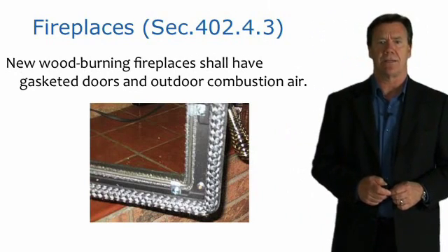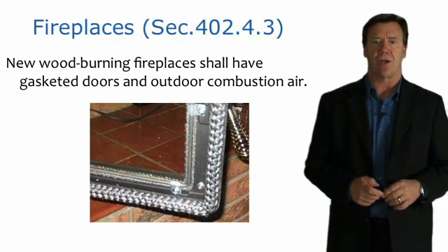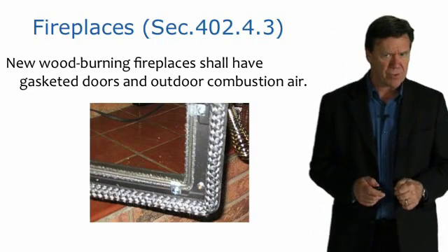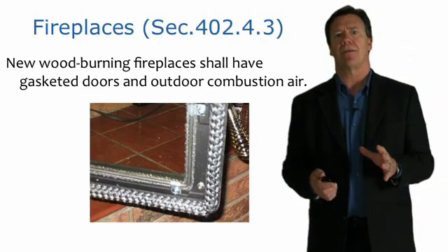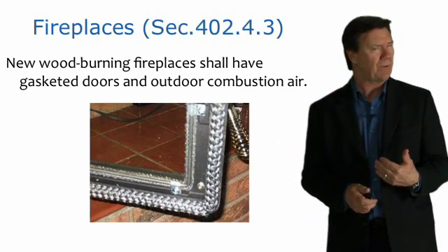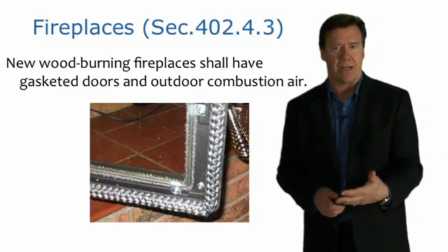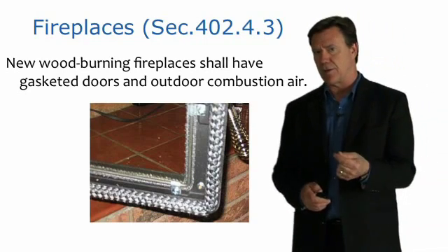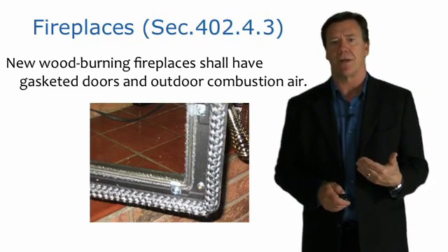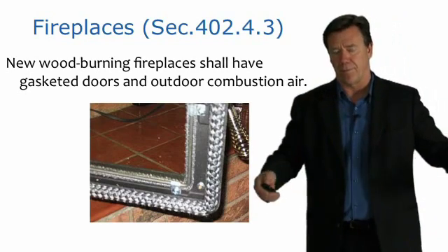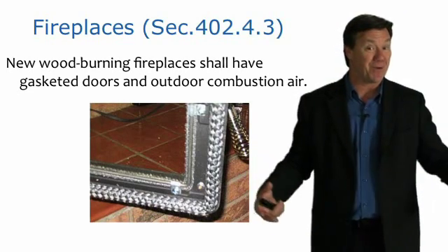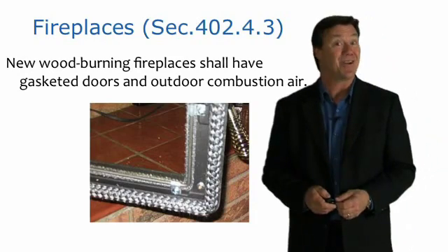Another code requirement is that wood-burning fireplaces shall have gasketed doors and outdoor combustion air. There have been reports around the country of fireplaces not engineered well enough to handle these gaskets, resulting in glass breakage — something the code has taken a serious look at. We definitely want outdoor combustion air for fireplaces so that indoor conditioned air isn't used for combustion and then must be reheated or re-cooled.